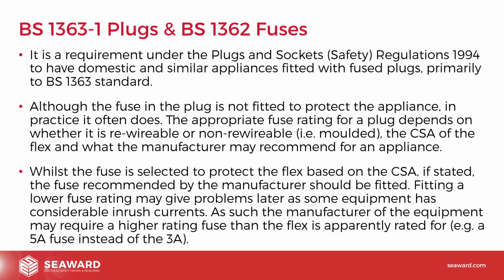Whilst the fuse is selected to protect the flex based on the CSA, if stated, the fuse recommended by the manufacturer should be fitted. Fitting a lower fuse rating may give problems later, as some equipment has considerable inrush currents. As such, the manufacturer of the equipment may require a higher rating fuse than the flex is apparently rated for, e.g. a 5 amp fuse instead of a 3 amp.